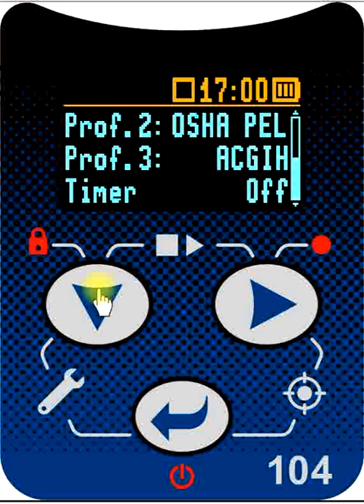Finally, this particular configuration file is not using the timers. The real-time clock in the instrument settings are currently disabled, meaning that the instrument will start and stop as we command from the keypad buttons.